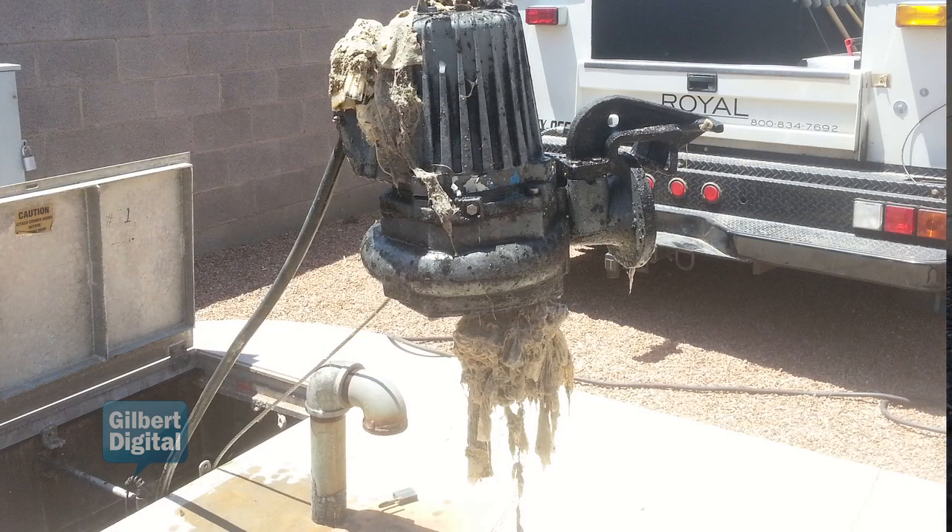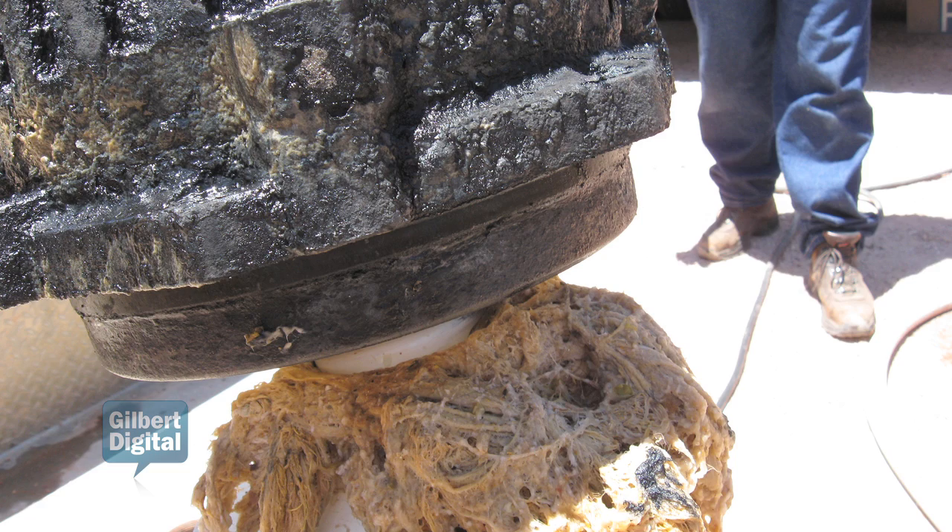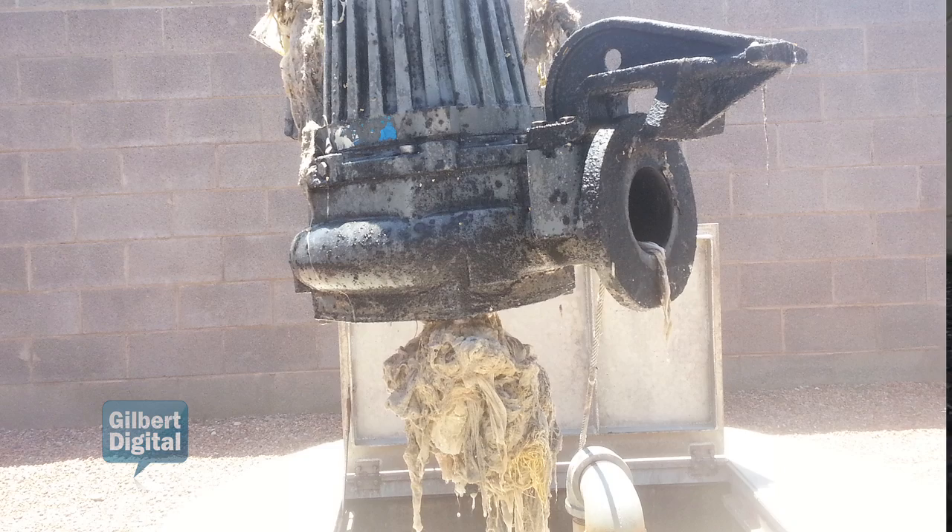When I say ragging up the line, I'm talking about blockages inside the sewer system. When I'm talking about ragging up the pumps, that means the pump impeller — it goes around and it seizes the impeller and can cause damage to the pump. We have to replace the pump more frequently or we have to do more maintenance on the pump.